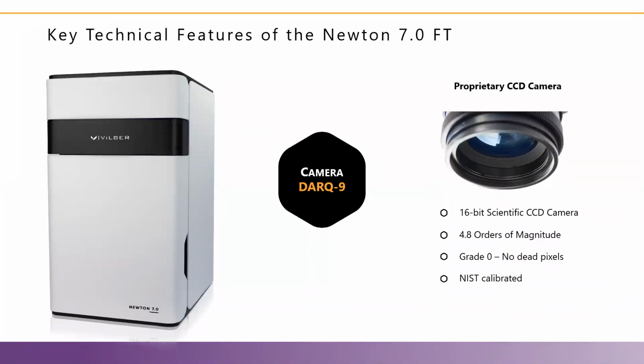I want to spend the majority of our time today discussing the key technical features of the Newton system. First, Vilber has developed this DARQ-9 camera, which is the latest generation of scientific CCD cameras, and it provides really unrivaled levels of sensitivity for both bioluminescence and fluorescence applications. The camera is a scientific 16-bit CCD camera, and it generates up to 65,000 gray levels with a dynamic range of 4.8 orders of magnitude. What this means is that very faint signals can be detected without saturating the strongest ones. The camera is also grade 0 with no dead pixels and is calibrated to NIST standards.